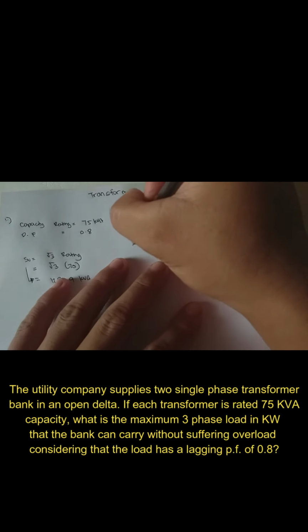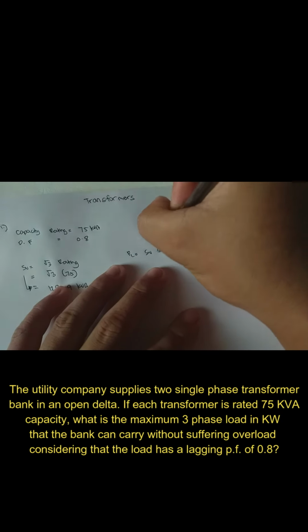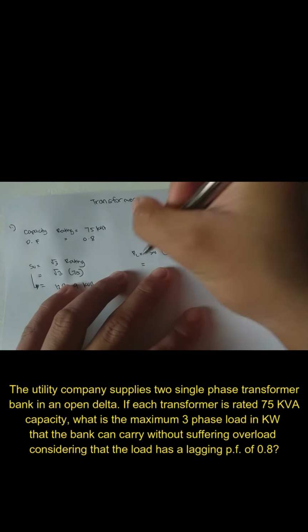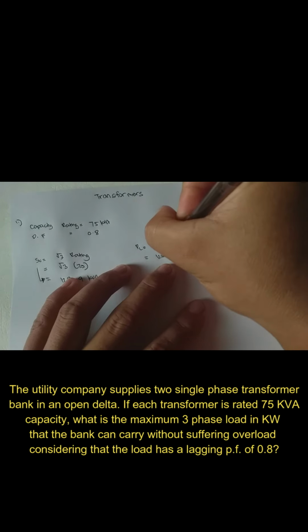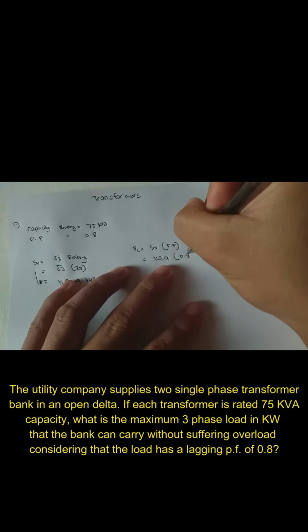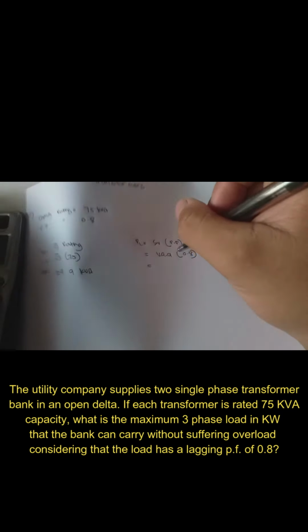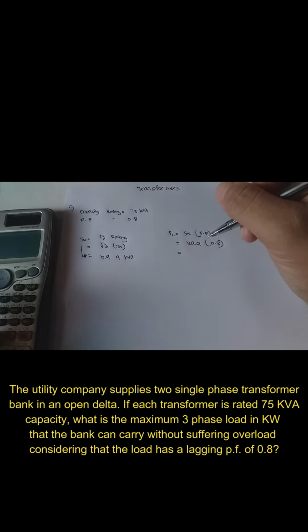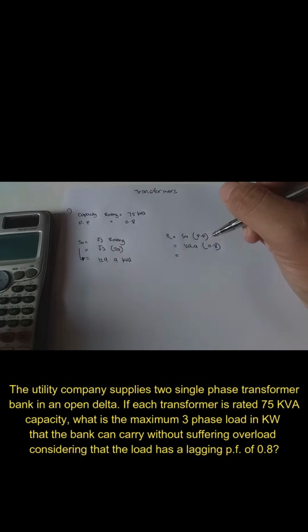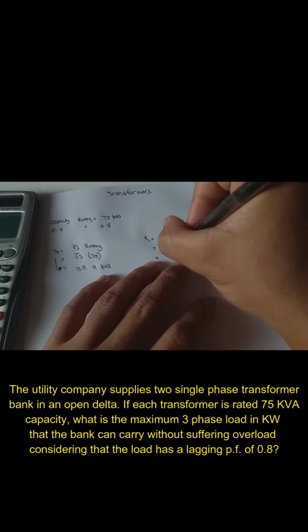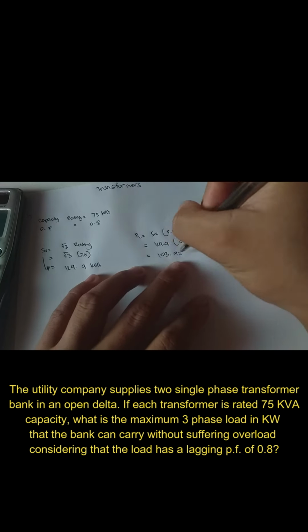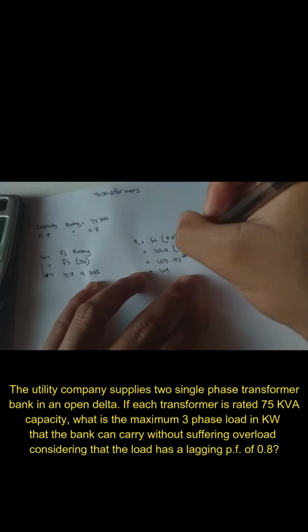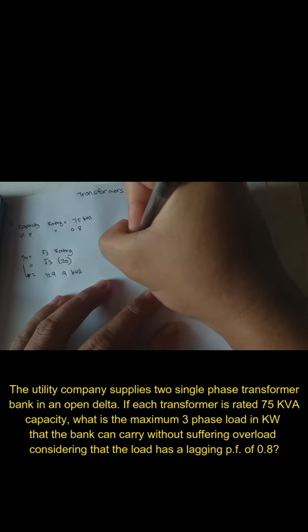kVA. Now, we will proceed to the maximum load, which is equal to the total apparent power times the power factor. So, we have 129.9 times the given power factor, which is 0.8. So 129.9 times 0.8, we have 103.92, or approximately equal to 104 kilowatts. That's the answer to problem number 1. And we'll proceed to problem number 2.